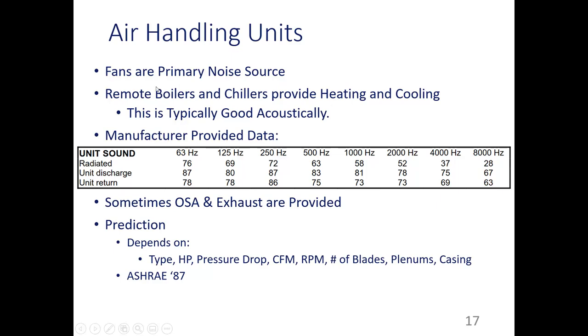So you have a remote boiler or remote chillers. They provide heat, and the refrigerant, for example, is piped to the unit and goes through the coil, and the fan just pushes the air through that. And it says here, this is typically good acoustically because air handling units are a lot quieter than the packaged units. Packaged units are when you include those condensing units. A lot of projects want to go with the packaged rooftop units. It's a pretty popular design, and it has its advantages, but that's not very good acoustically. Those condensing units add a lot more noise.